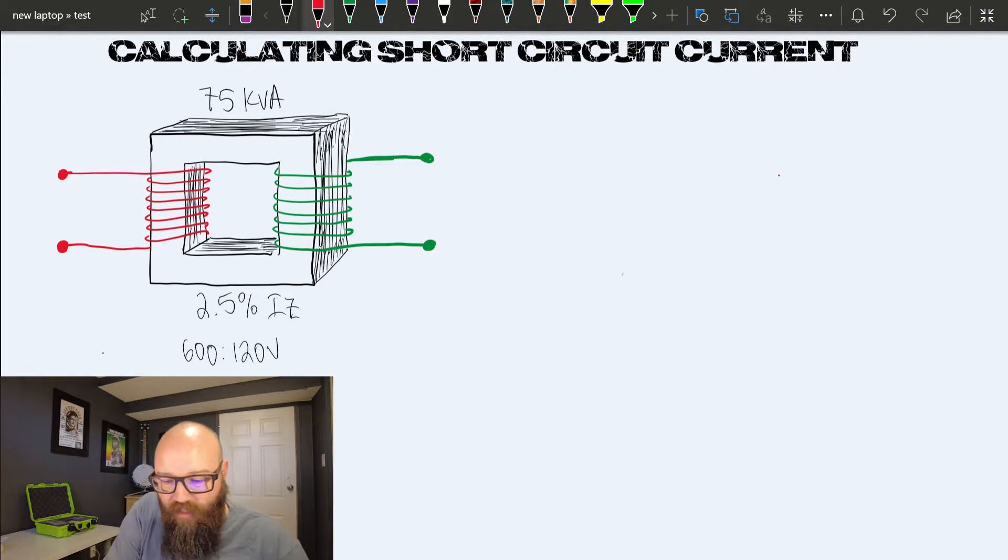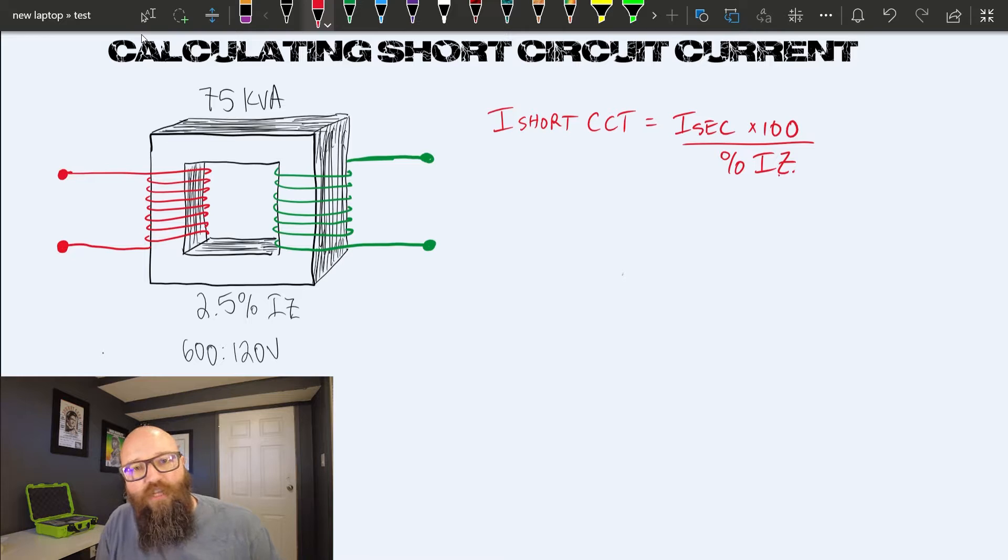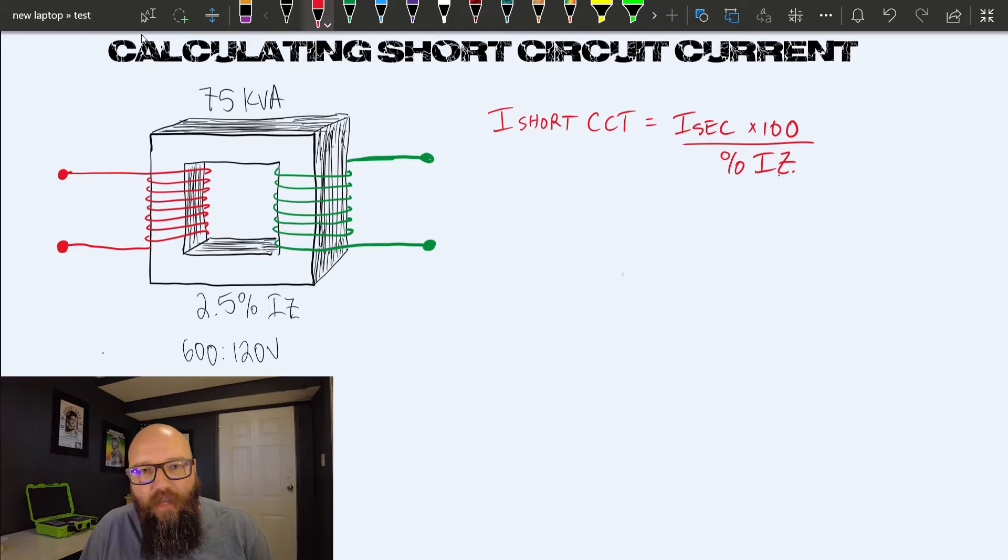Before we get rolling, let's write out our formula. I short circuit equals current on the secondary times 100 divided by percent IZ. There are variations of this formula. I like to use I secondary times 100 because it automatically converts that percent impedance to its decimal form without having to convert it in the formula. That way I can just grab the actual raw percentage—I can use 2.5 in this example. That's what that times 100 does.